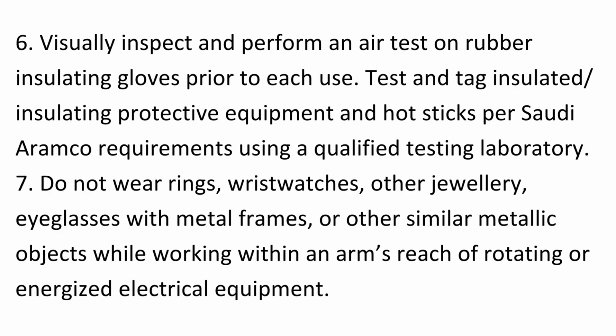6. Visually inspect and perform an air test on rubber insulating gloves prior to each use. Test and tag insulating protective equipment and hot sticks per Saudi Aramco requirements using a qualified testing laboratory. 7. Do not wear rings, wristwatches, other jewelry, eyeglasses with metal frames, or other similar metallic objects while working within an arm's reach of rotating or energized electrical equipment.